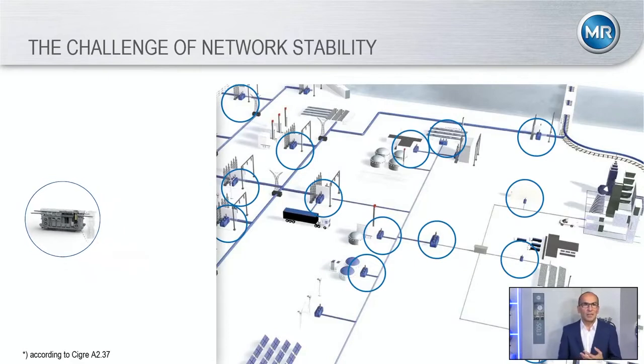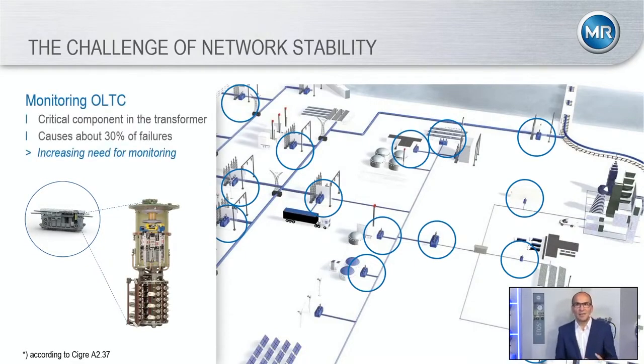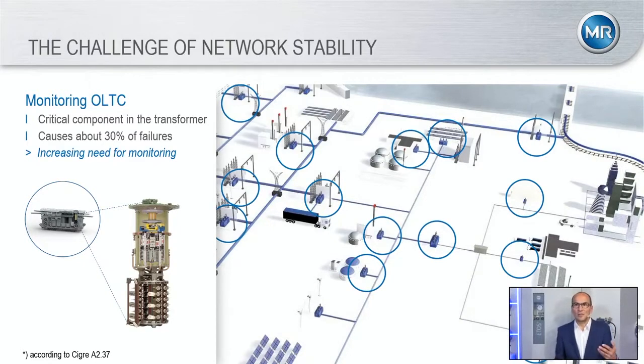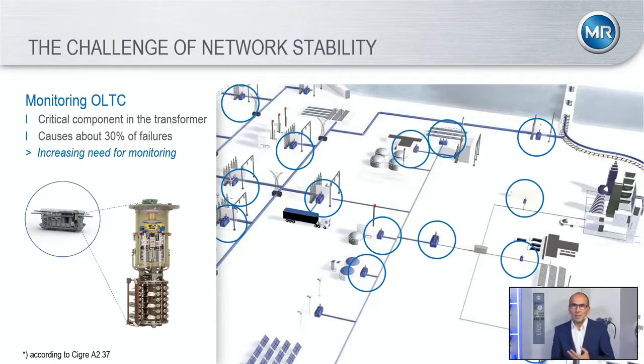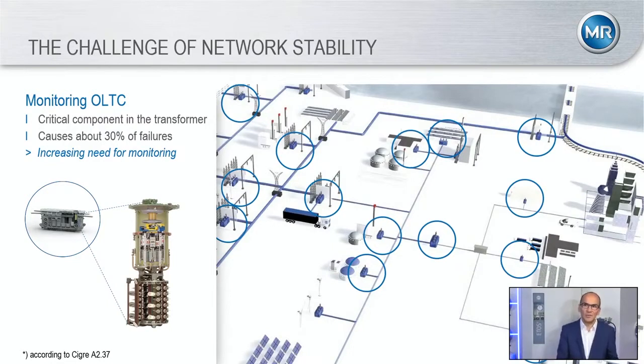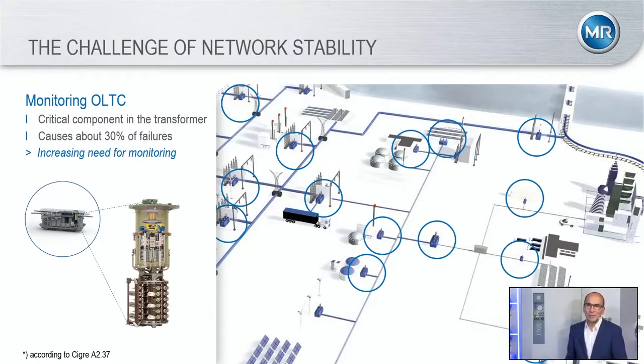This constant monitoring is done in various ways. It aims at extending and establishing new maintenance practices, such as condition-based maintenance, which allows you to extend the maintenance periods of the OLTC as much as possible. It includes self-monitoring to ensure the switch is working in perfect condition without any disturbances. The monitoring also gives more flexibility in transformer utilization, increasing load and performance while reducing cost. With that constant monitoring of the OLTC, we aim at maximum availability and avoiding any unplanned disturbances or irregularities.